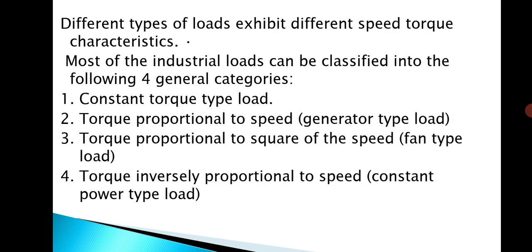The four general categories are: constant torque type load, torque proportional to speed which is generator type load, torque proportional to square of the speed which is fan type load, and torque inversely proportional to speed which is constant power type load. These are the four types of industrial load categories depending upon torque-speed characteristics.